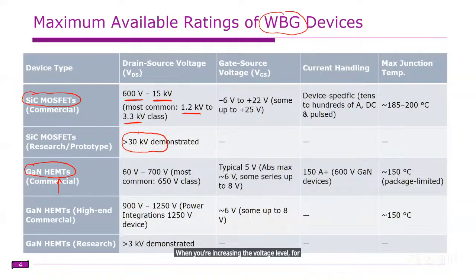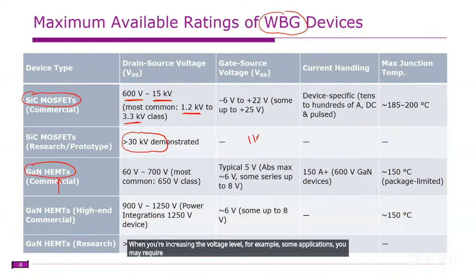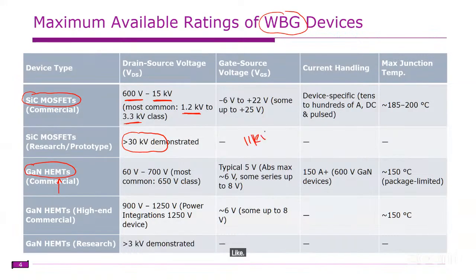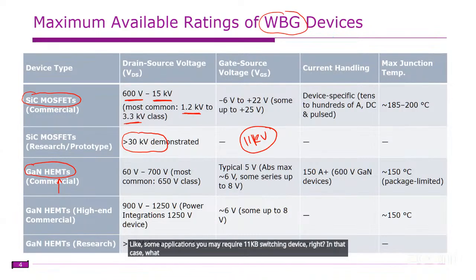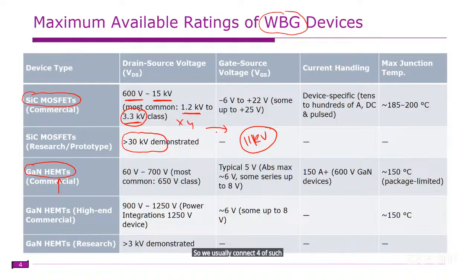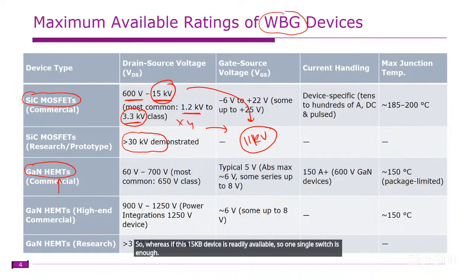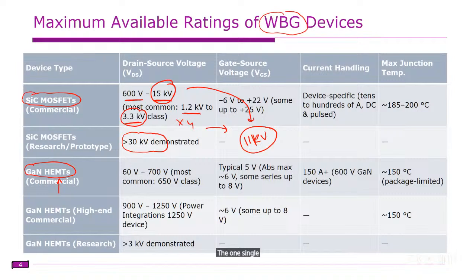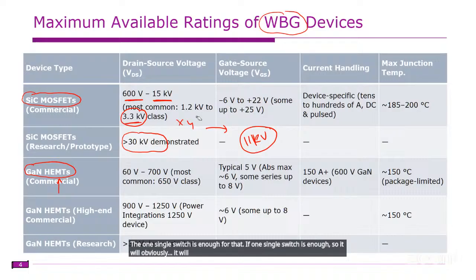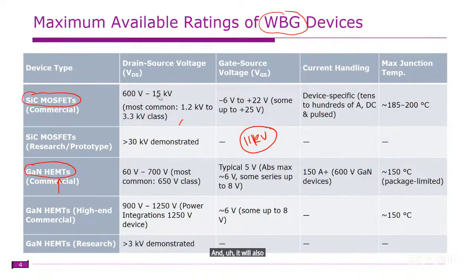For example, some applications may require an 11 kV switching device. Normally, if we select a 3.3 kV device, we connect 4 of them in series to get 11 kV. Whereas if a 15 kV device is readily available, one single switch is enough. This reduces the size and also increases the reliability.